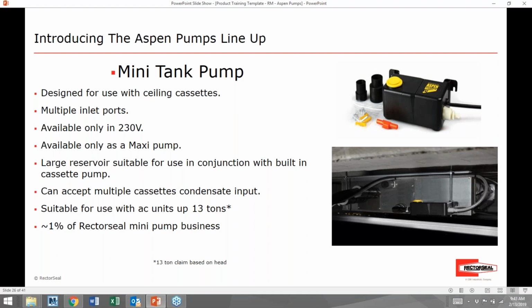Now, what we've seen is, because this is a Maxi and it's suitable for up to 13 tons, we've often seen where there might be 4 or 6 1-ton units serving a large area in a business, for instance. And what we see is we use the Mini tank pump as a central point of distribution for the condensate. So all 6 or 8 of those units might pump into this Mini tank pump, and then allow the Mini tank pump to pump up again as high as 50 feet. Now, this Mini tank pump is a niche market, and it's only less than 1% of Rector Seal's total pump business.